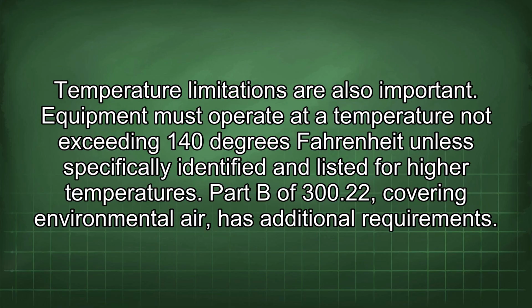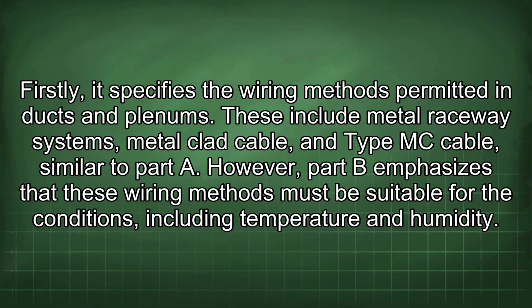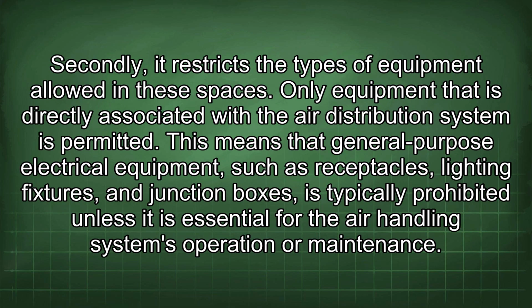Part B of 300.22, covering environmental air, has additional requirements. Firstly, it specifies the wiring methods permitted in ducts and plenums. These include metal raceway systems, metal-clad cable, and Type MC cable, similar to Part A. However, Part B emphasizes that these wiring methods must be suitable for the conditions, including temperature and humidity. Secondly, it restricts the types of equipment allowed in these spaces. Only equipment that is directly associated with the air distribution system is permitted. This means that general-purpose electrical equipment, such as receptacles, lighting fixtures, and junction boxes, is typically prohibited unless it is essential for the air handling system's operation or maintenance.